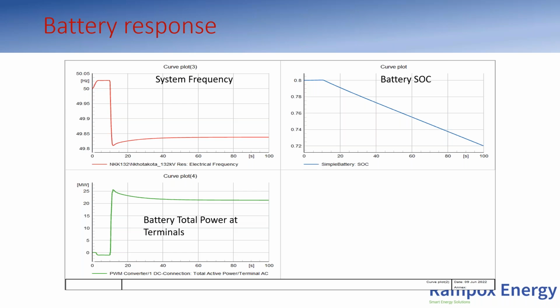If we increase the amount of reserves to a level greater than what we have now, we've seen that it's not helping because the droop levels are too high, and the response from the governors is too slow because they've got mechanical time constants. For them to react takes time, and we've seen that it doesn't help. There's a point where you get diminishing returns—so much reserves with so little impact. Through studies, everybody in the world has seen that governor response is no longer really capable of dealing with this phenomenon. So where do we need to go?